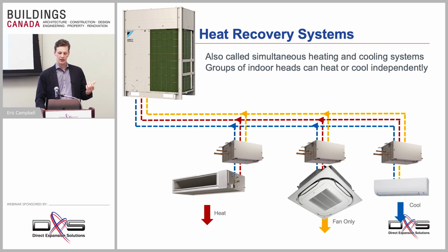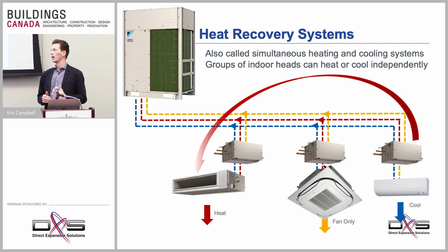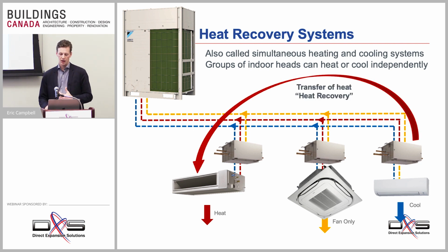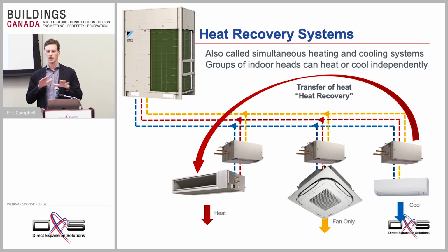But one of the key things here is that there's actually a transfer of heat, which is why we call it a heat recovery system. Because of this transfer of heat, the highest efficiency you can get is when you have about equivalent amounts of heating and cooling at the same time. So in your shoulder seasons, as opposed to a heat pump system where you want to zone for different exposures, with heat recovery, you want to do the opposite. Now you want to zone so that you have as many different exposures on the same system so that we can take as much advantage of heat recovery and therefore reduce the operating costs of the system.